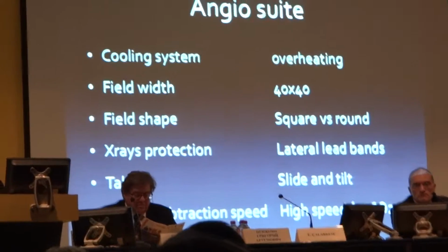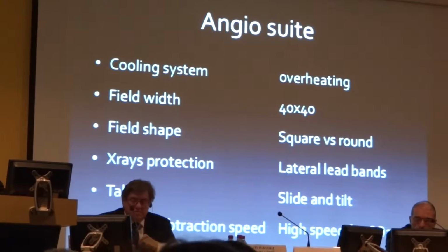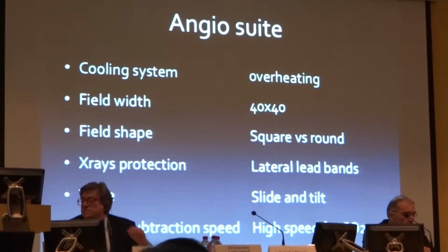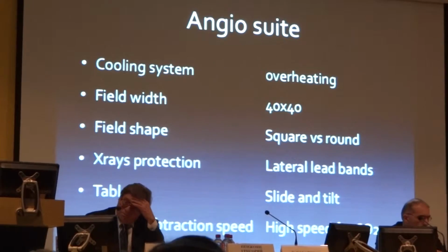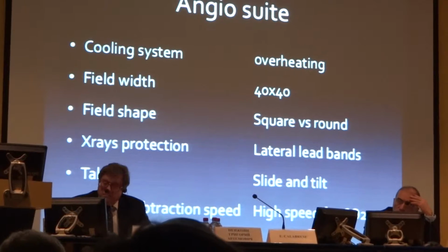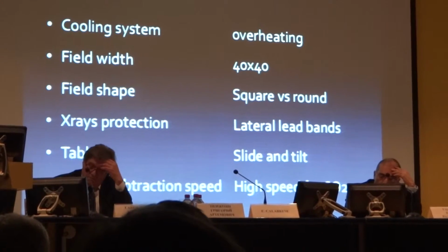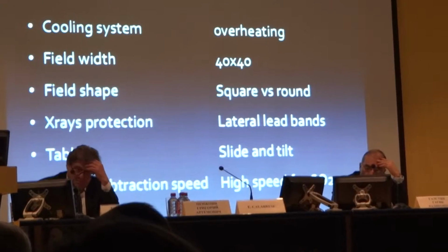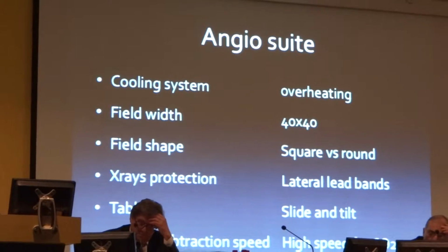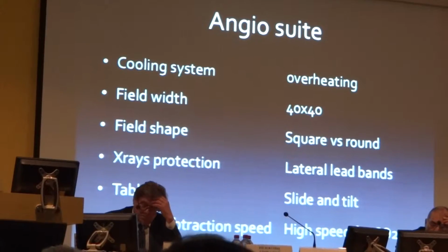In many countries, surgeons are using a portable system, and this portable system has an inferior resolution, and more than the resolution, an inferior capability of heat dissipation, of getting rid of the heat that they produce with long monitor time. This makes the system overheat and makes portable systems surely inferior. So whenever you are able to get a fixed system, it will be a great advantage, with large field width and square or rectangular fields. Round fields, or image intensifiers, are not available anymore on the market.